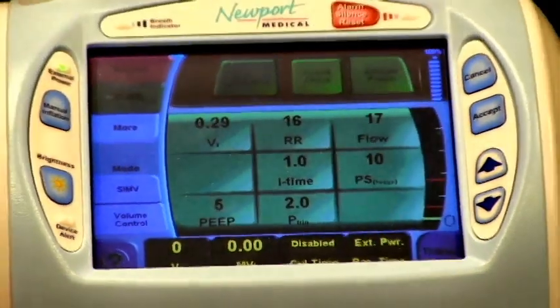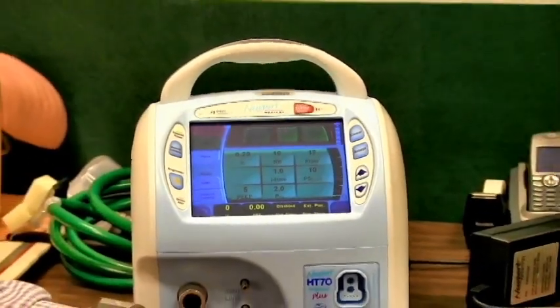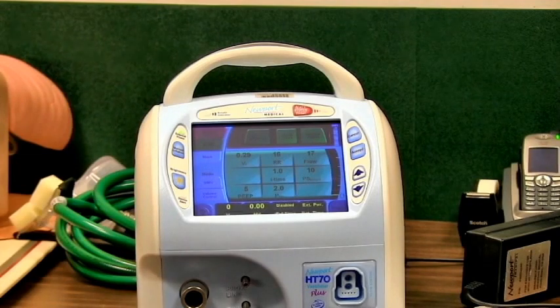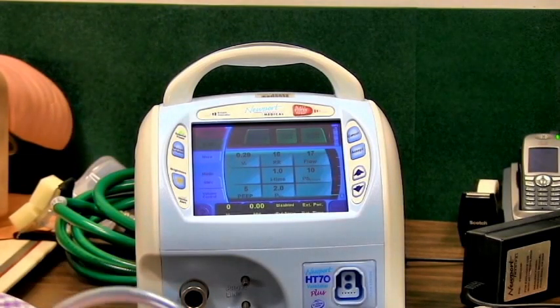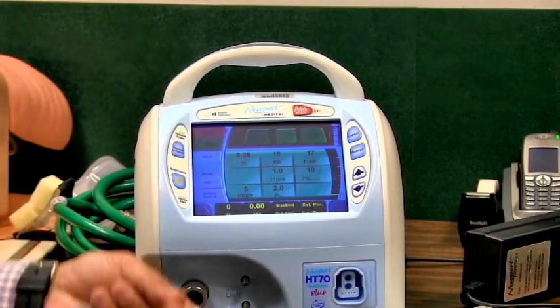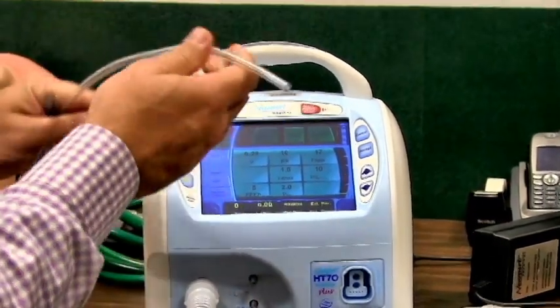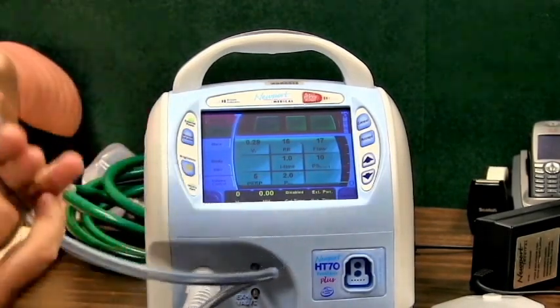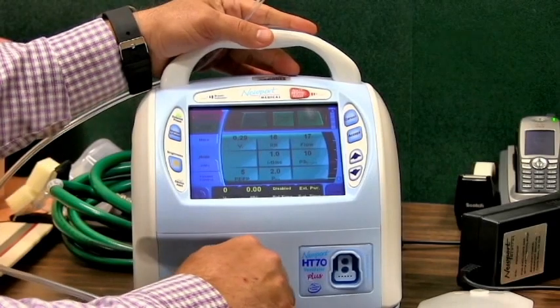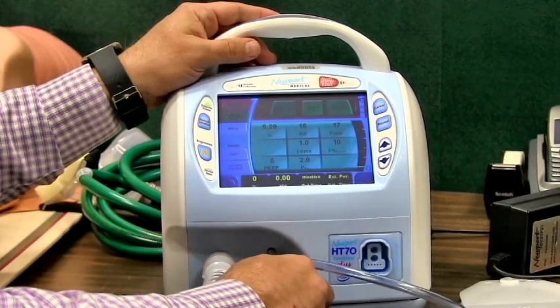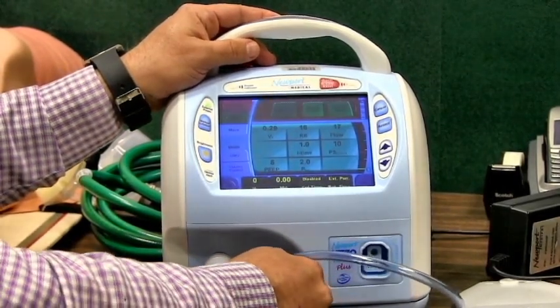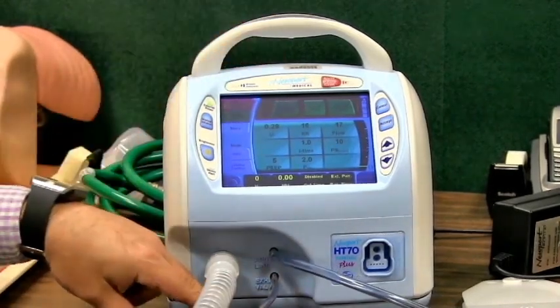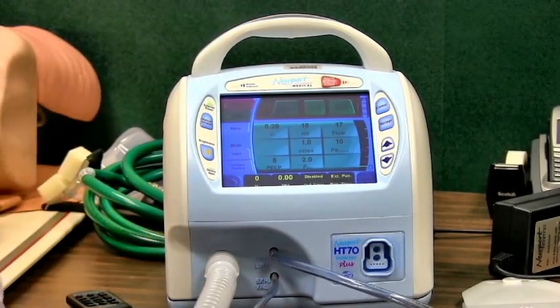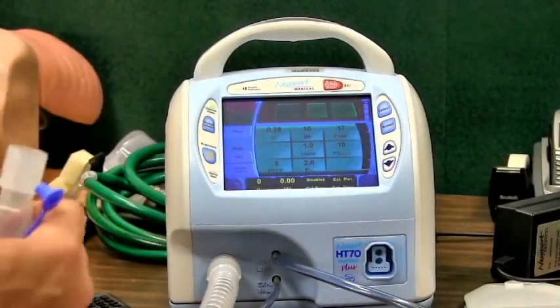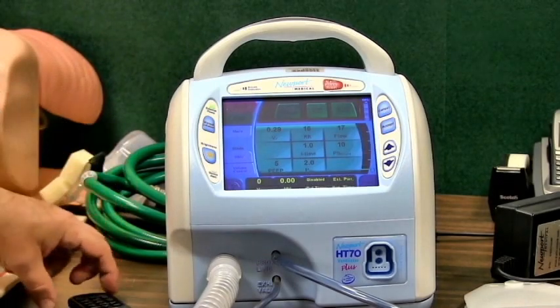So in order to do the circuit check, as we zoom out here, I'm going to show you with the circuit. The first thing that you do is take your circuit and plug the circuit ends in, just like I told you earlier, ends inside. So your circuit goes into here. The larger diameter line, or the prox air line, goes on top, and you're just going to push it in until it gets past the hub. The next one is going to be your exhalation valve. You're just going to connect it again just till it gets past a hub or two, but make sure that it's just connected. On the other end here, you're going to have your circuit piece, and you're just going to follow the prompts as you go through your circuit check.